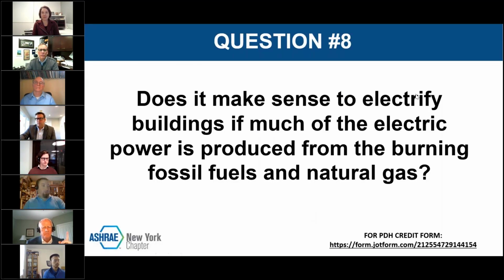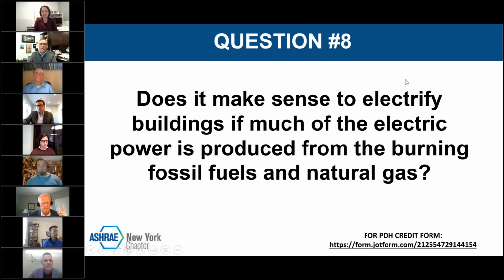Well, doesn't that play into the heat pump aspect, where you're basically switching from cooling-only to heat pump equipment so that you could take advantage of getting the extra heat when you need it, and that same electrical connected load is used in ways then? Right. Yeah, and using heat injection from something like the existing boiler plant or steam network might be necessary from the onset if you're going to go with that chiller heater approach, electrical means. But developing that more complex roadmap is usually required for these existing facilities.